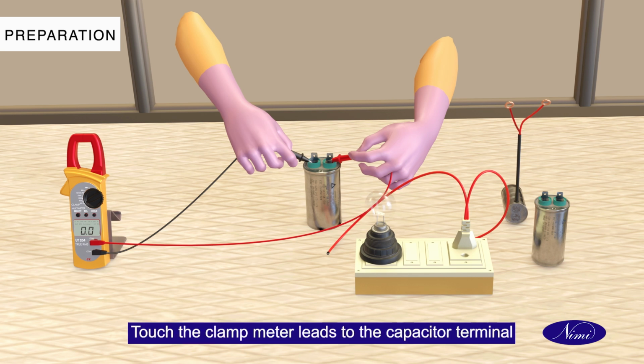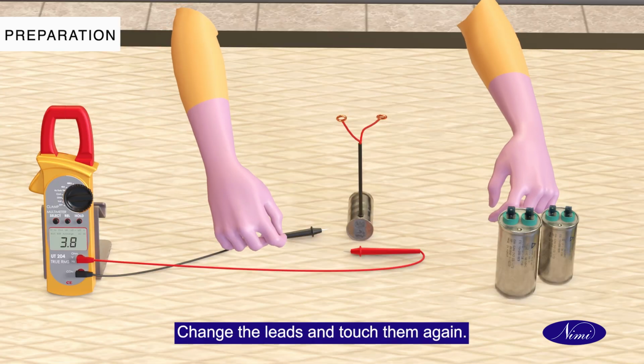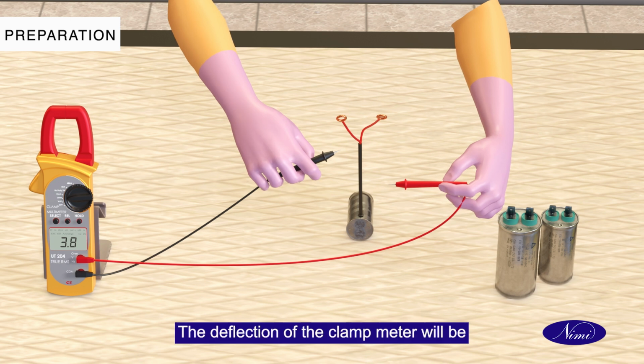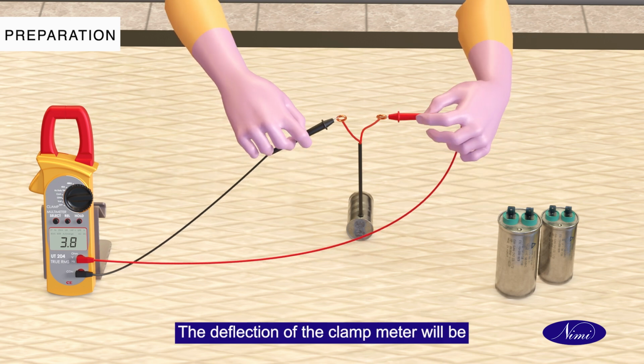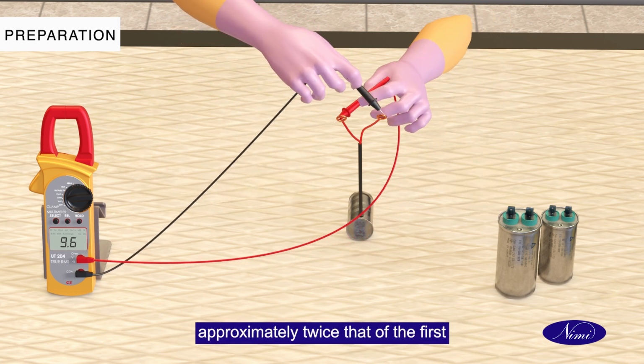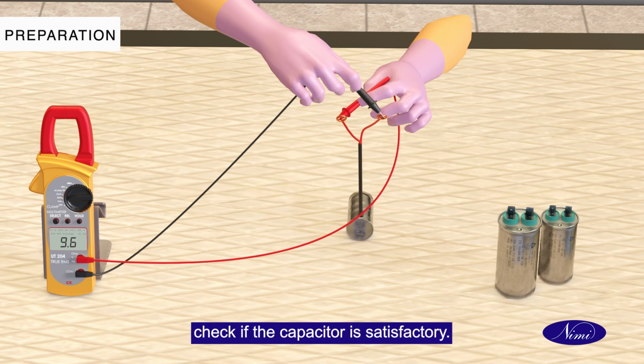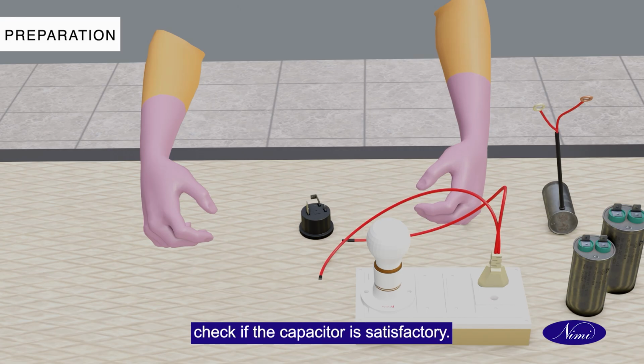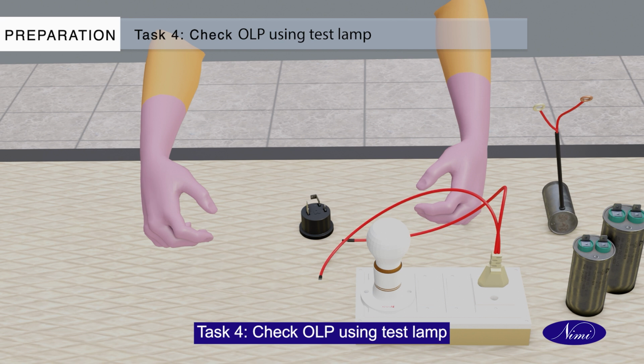Touch the clamp meter leads to the capacitor terminal and note the deflection of the clamp meter. Change the leads and touch them again. The deflection of the clamp meter will be approximately twice that of the first check if the capacitor is satisfactory. Task 4. Check OLP using test lamp.